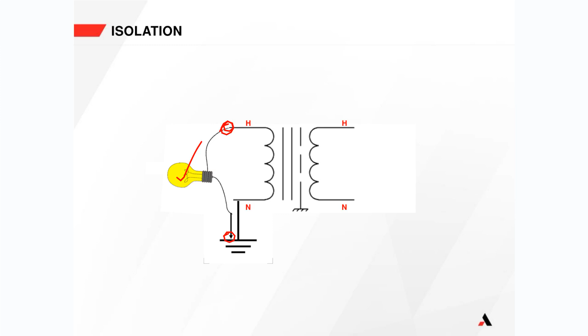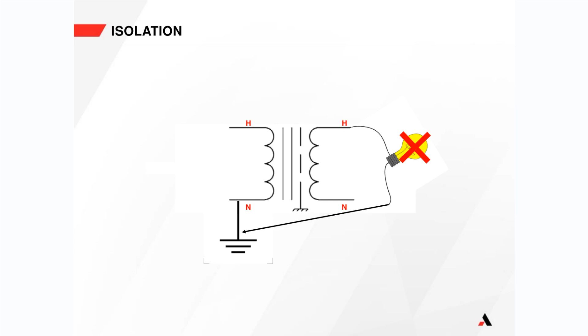if we added a rectifier, so AC in, DC out to the output of this system, therefore, when we connect a battery to the output of that rectifier, there is no reference to ground within our system. So therefore, if somebody goes to work on the battery, takes measurements, or wants to clean some terminals or something like that, it's very difficult for that worker to get an electrical shock when you have an isolation transformer, because there is no direct connection down to ground. Okay, now obviously, yes, if they went from the full positive to the full negative of the DC battery, they could subject themselves to an electric shock. But from any post of the battery down to ground, they would not get an electric shock.